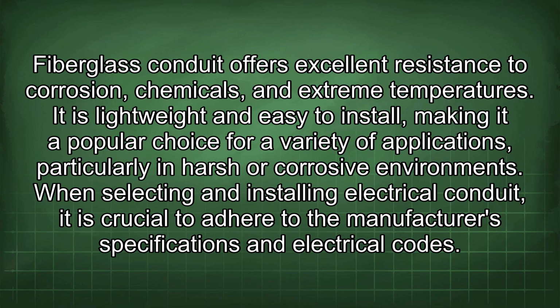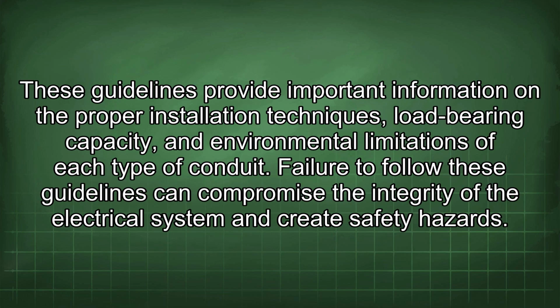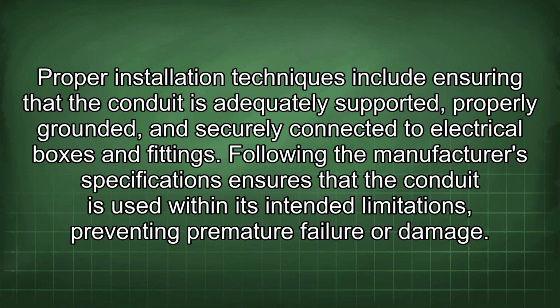or corrosive environments. When selecting and installing an electrical conduit, it is crucial to adhere to the manufacturer's specifications and electrical codes. These guidelines provide important information on the proper installation techniques, load-bearing capacity, and environmental limitations of each type of conduit. Failure to follow these guidelines can compromise the integrity of the electrical system and create safety hazards. Proper installation techniques include ensuring that the conduit is adequately supported, properly grounded, and securely connected to electrical boxes and fittings. Following the manufacturer's specifications ensures that the conduit is used within its intended limitations, preventing premature failure or damage.